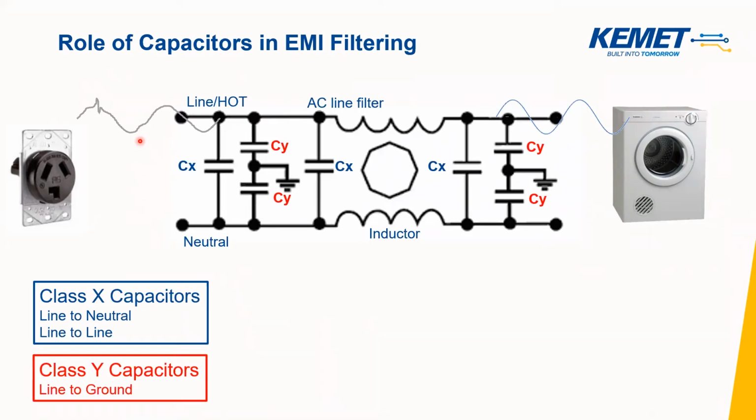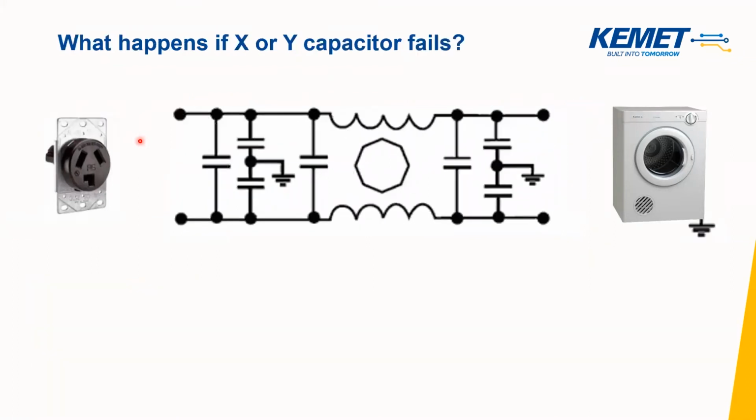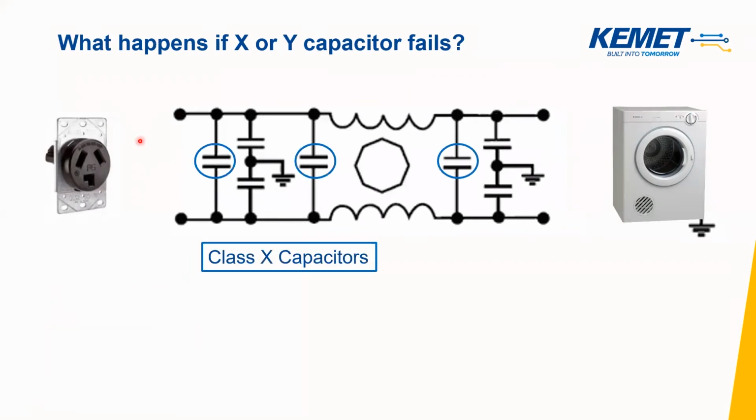typically, capacitors which have requirements from IEC that need to be fulfilled, because if there is any failure that happens in any of these capacitors, which could be a reality because you have these high voltage, high frequency transients that could seep into any of these capacitors. So this could lead at times to, let's say if you have a failure or a short across your X capacitor, perhaps a blow of the fuse or fire.